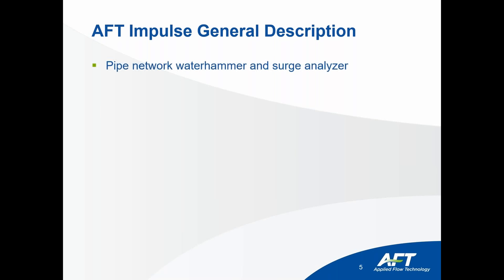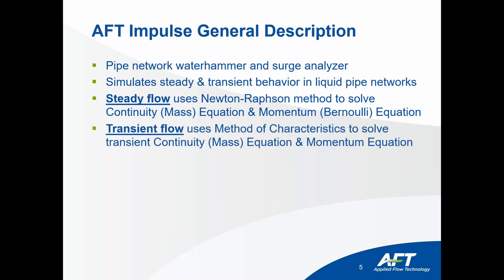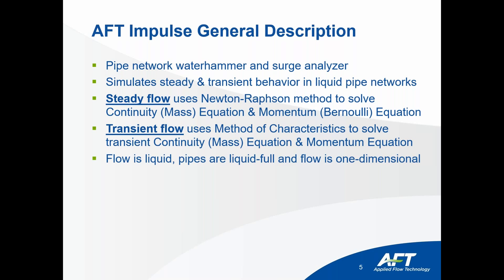AFT Impulse is an excellent pipe network surge analyzer. Impulse has a steady-state solver because initial conditions need to be established before the transient analysis can begin. It uses the same Newton-Raphson steady-state mass and momentum balance solver that Fathom does. For transients, the method of characteristics is used to solve the transient mass and momentum balances. Key assumptions: flow is liquid, all pipes are liquid-full, flow is one-dimensional, and wave speed is constant during the transient.